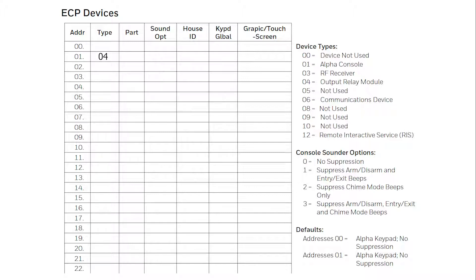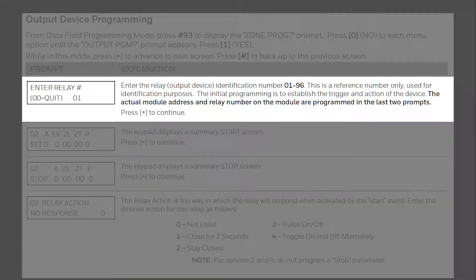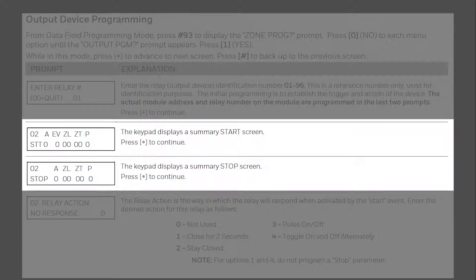For this programming, continue to press 0 for no until you reach output programming. Press 1 for yes. The first question will ask for the relay number. This is simply a line of programming for a single relay. Multiple output functions can be programmed for the same relay if needed. For your first relay, enter in 01, then press star. The summary screen will show if there is already something programmed here. If everything is listed as 0 on the bottom row, then this relay is clear for use. Press star to move forward.